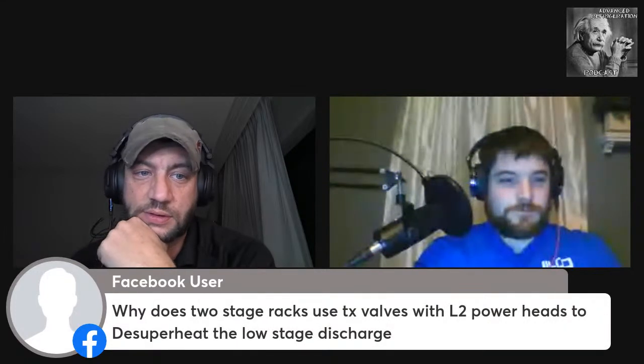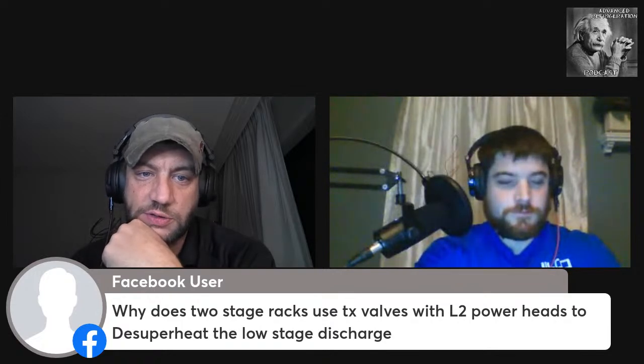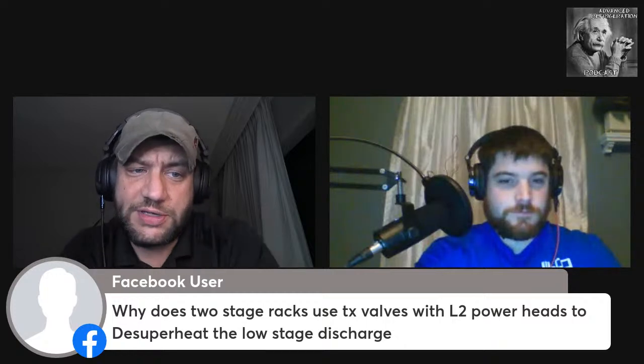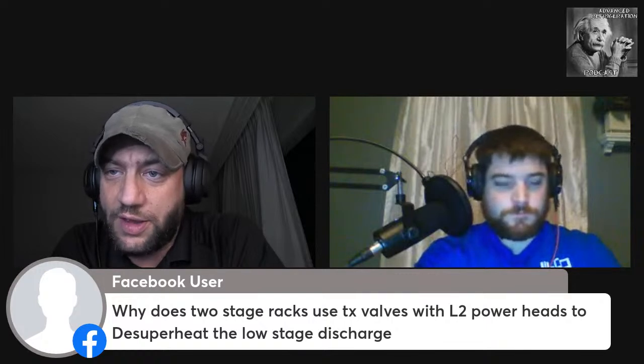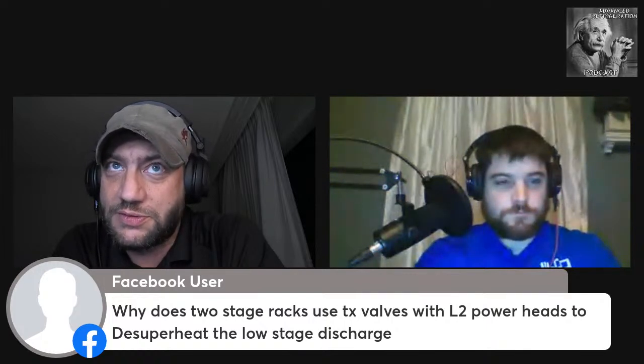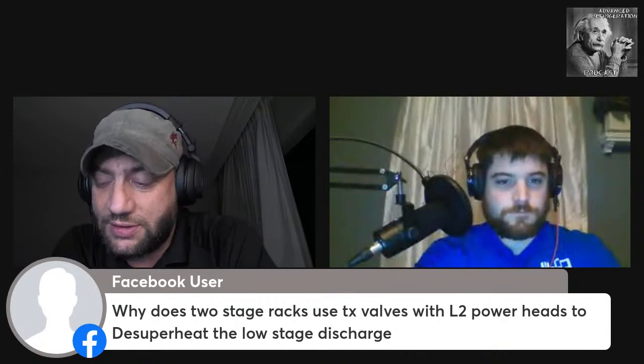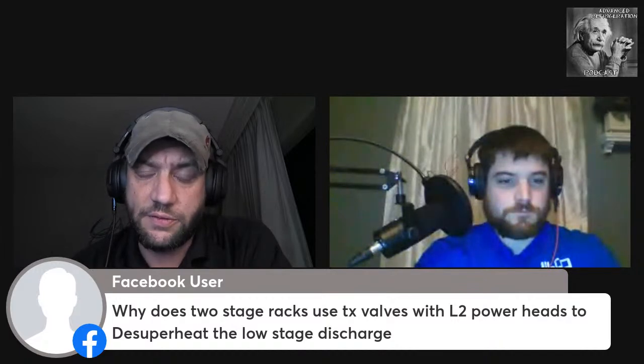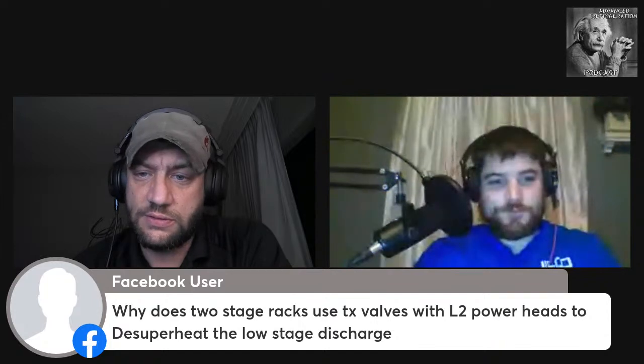Why do two-stage racks use TX valves with L2 power heads to desuperheat low-stage discharge? Because you're basically pumping discharge gas into the back end of the compressor off of the primary stages. So to help cool that process, you basically have those liquid injection valves throwing liquid in there. That's what the L2 power heads are, right? They're the liquid injection ones. I'm going to be honest with you, I've never looked at an L2 power head. No, okay.